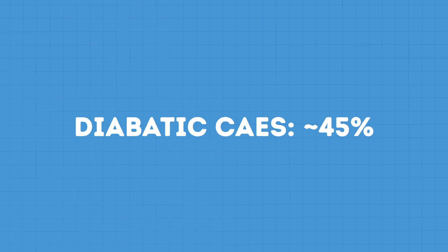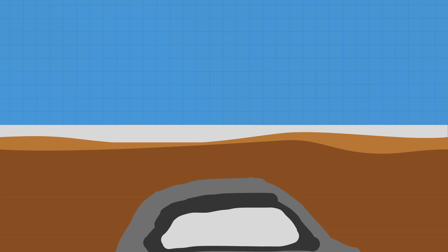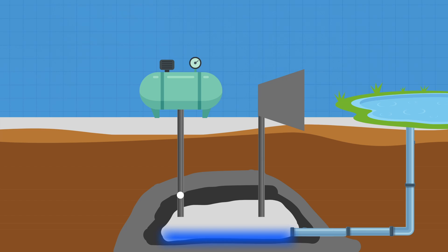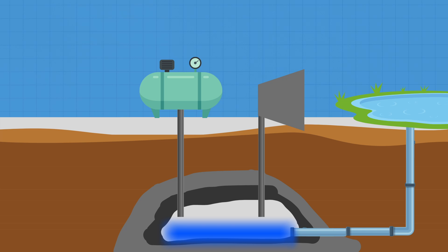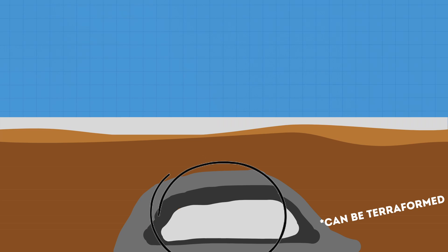Another important step of the process is keeping the cavern at a constant pressure. The way plants do that is by using water. When compressed air flows into the cavern, water is pumped out and stored in a reservoir. When the compressed air goes back out, in order to maintain the pressure, water is pumped in to replace the gaps the air left.